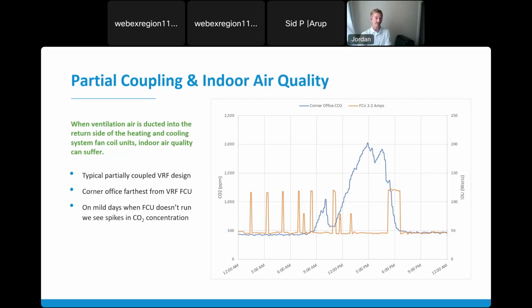Then the temperature warms up, and it's a 50 degree, 55 degree day. So there are no calls for heating or cooling for quite a while while people are in the office, and CO2 spikes in the space. This is because the ventilation air is not being delivered to many of the end of the run offices. This is a fan coil unit serving about 9 offices, and the furthest offices away are often starved for ventilation on these mild days. This happened throughout the spring and fall season in this particular office, and we've seen this in basically every partially decoupled design we've seen. So we feel that fully decoupling, delivering ventilation air directly to the conditioned space, is a far better approach for ensuring that ventilation air gets delivered consistently during occupied hours.